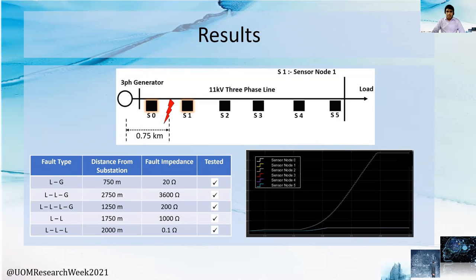Moving to the results, let's consider a line-to-ground fault with 20 ohms fault impedance, occurring at 750 meters away from the substation. The fault is between sensor node 0 and sensor node 1. This plot shows a noticeable variation between the waveforms of sensor node 0 and 1 in white and yellow colors. It is clear that the highest peak value difference exceeds between the waveforms of sensor node 0 and 1, so we can clearly identify node 0 and 1 as the faulty segment. We verify the accuracy of our algorithm across various fault types, differing fault distances from the substation, and fault impedance levels.